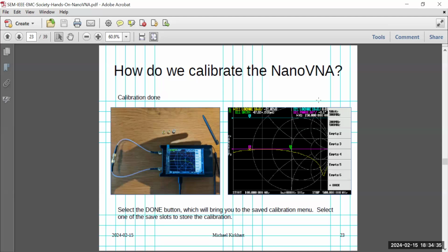Wow, awesome, that worked. But we're going to do a check. The check is good because if you see measurements that look funny, you can go back and check if the calibration is okay. Then you can go through a quick calibration step. You don't have to press any buttons during that check, you just connect the calibration standards and look for certain things on certain graphs.